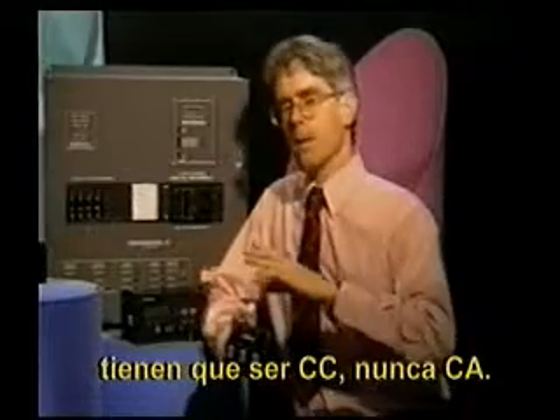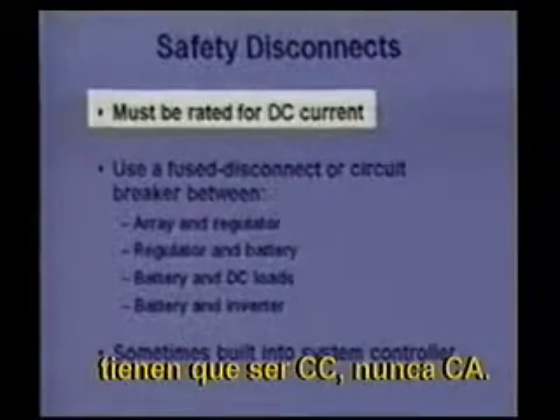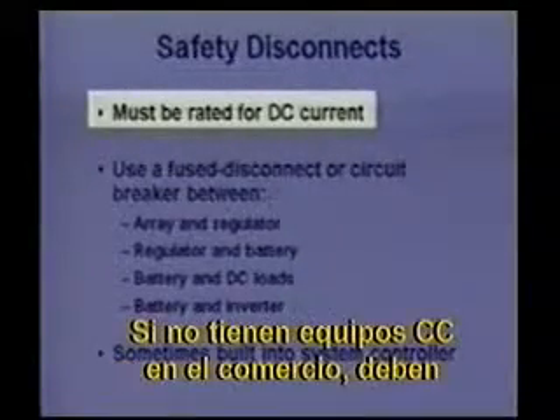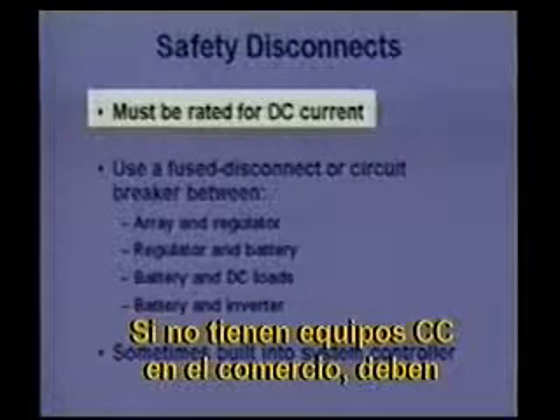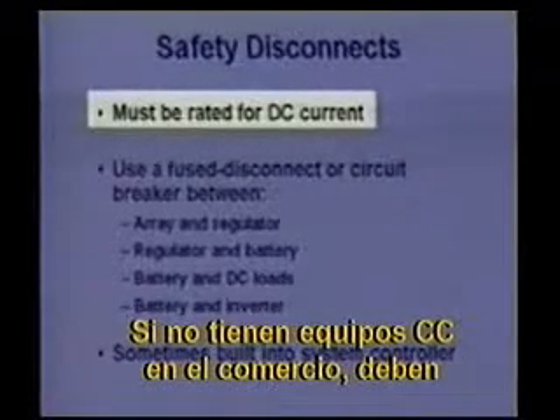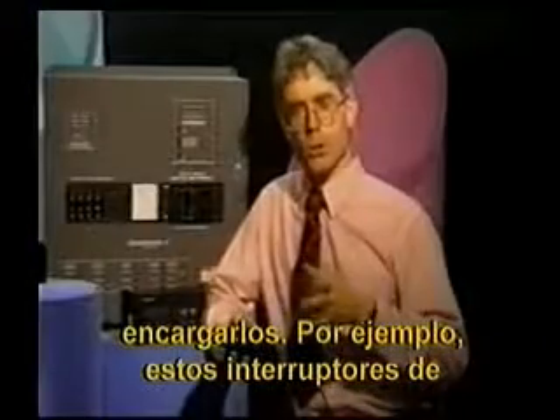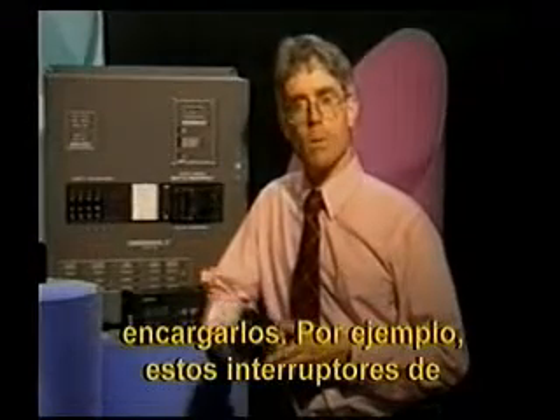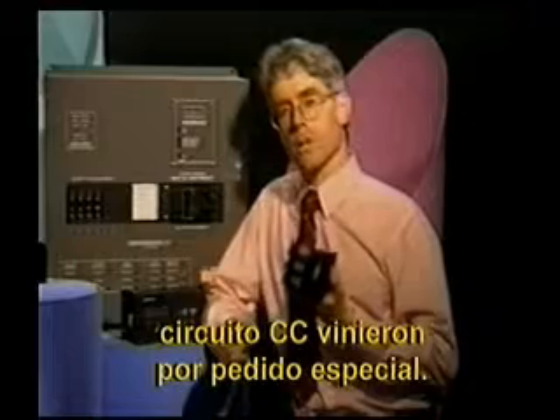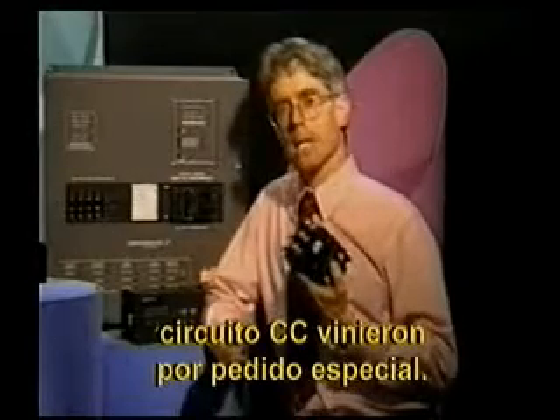A concern to keep in mind is that all of this switching that we need to be able to do has to be done with DC-rated devices. Don't just grab standard AC products off the supplier's shelf. We have to choose or perhaps even order DC-rated equipment. For example, these circuit breakers are a special order, DC-rated item.